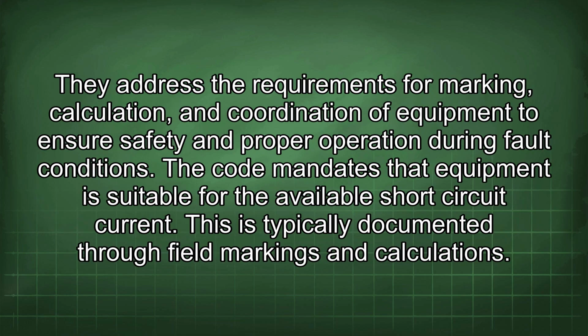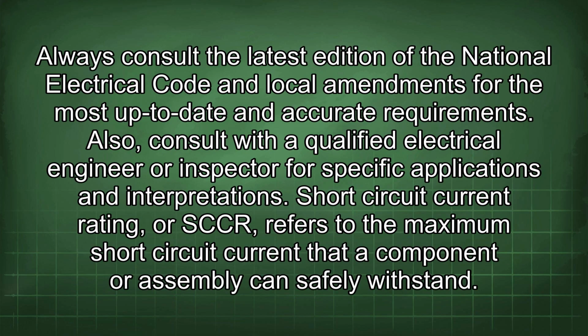They address the requirements for marking, calculation, and coordination of equipment to ensure safety and proper operation during fault conditions. The code mandates that equipment is suitable for the available short-circuit current. This is typically documented through field markings and calculations. Always consult the latest edition of the National Electrical Code and local amendments for the most up-to-date and accurate requirements. Also, consult with a qualified electrical engineer or inspector for specific applications and interpretations.